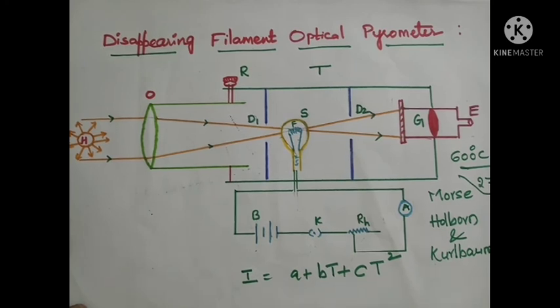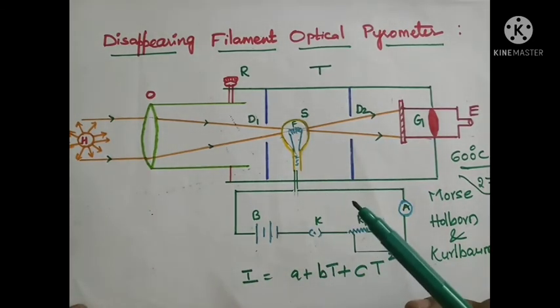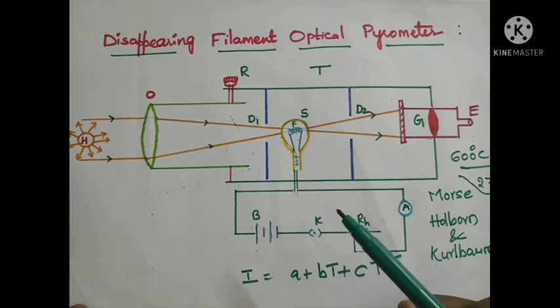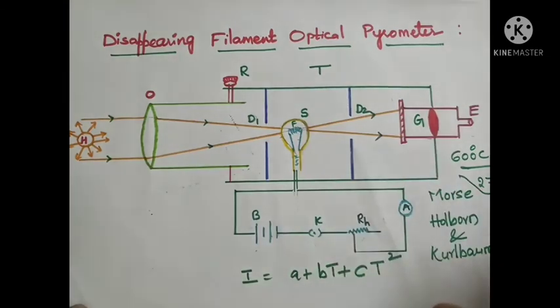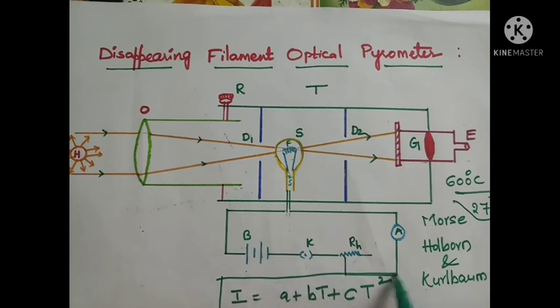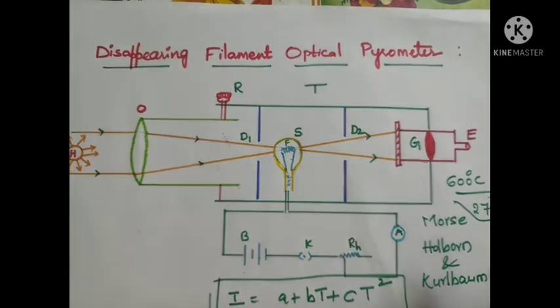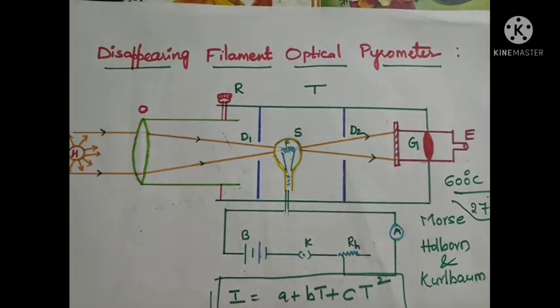Even if the experimental object is not a black body, the corrections may be easily applied and are relatively small. This is all about the disappearing filament pyrometer — very simple structure and a simple formula: I = a + bT + cT², where I is the current flowing through the circuit and T is the temperature of the hot body to be measured.